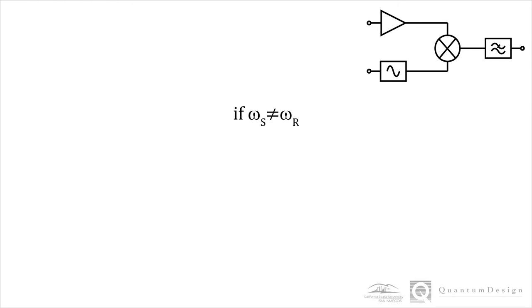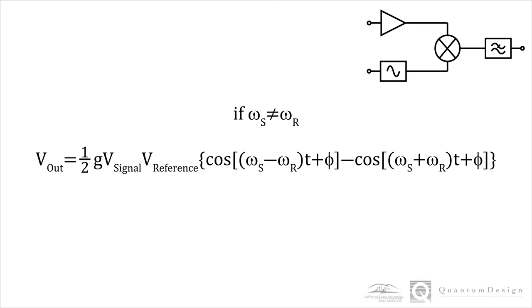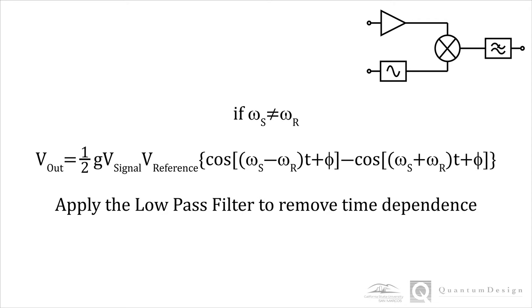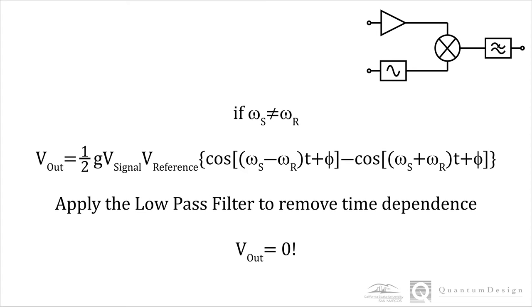The advantage of this technique is made clear when the signal frequency is not the same as the reference frequency. We take the mixer output as before, and now both cosine terms vary in time. The first term has a frequency corresponding to the difference in frequencies between the signal and the reference, and the second term has a frequency corresponding to the sum frequencies of the signal and the reference. By applying the low-pass filter, ideally, there is no output. We will soon demonstrate this using the Electronic Transport Option, or ETO, module of the VersaLab.